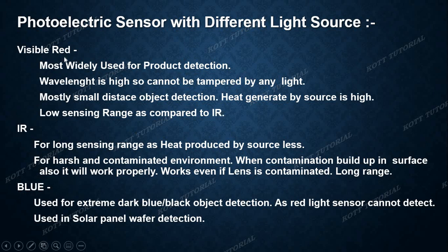The reason is that if I am using a visible red light or an IR sensor, complete light incident on the product would be absorbed. But in case of blue light, it's not the same. Blue light source photoelectric sensor can successfully detect perfectly black body like solar panel wafer. For the solar panel wafer detection, we use blue light source photoelectric type sensors.